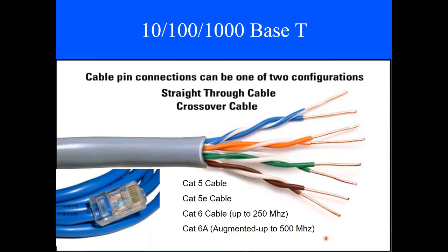Just so you know, 6 is not necessarily better than 5, since obviously we get into a lot of industrial applications and utility applications. What we find is to get 6 and 6A, you've got to have less capacitance in the system, which means it's more susceptible possibly to noise. So if you're going to use these cables, I recommend you use a shielded cable to help protect it. But sometimes 5 is better than 6.